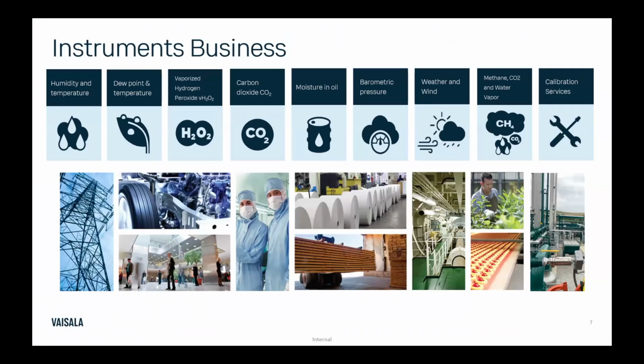And then this is the last slide before we get into the real information, but I want to highlight this before we dive too far into humidity and temperature, and include this slide to showcase the offering of the parameters that we have for measurement solutions. So humidity and temperature are our main and most commonly measured parameters. However, we also have sensors for dew point, vaporized hydrogen peroxide, carbon dioxide, moisture in oil, barometric pressure, weather and wind, which we will touch on briefly, methane and CO2 for biogas, and then a full line of calibration services for all of our instruments as well. I'm happy to answer any questions on any of these. However, today's information will be mainly dedicated to humidity along with outdoor weather measurement.